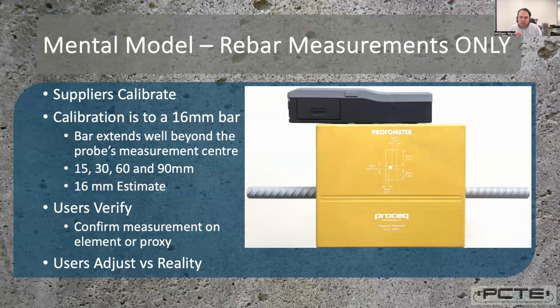The thing about a measurement is it's not a single moment of the number. So if you go and take out and look at your calibration certificate, you'll see that each measurement is taken 5 times. And they may be the same, or there may be 1 or 2 with a slightly different value. And what we consider our measurement to be is the average of those 5 values at each depth.